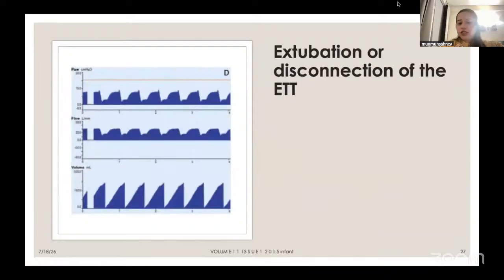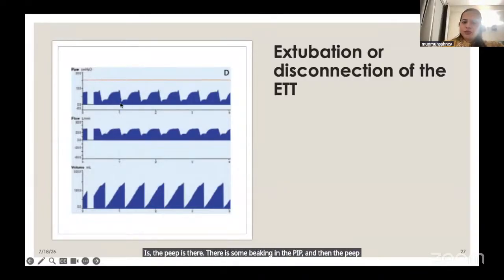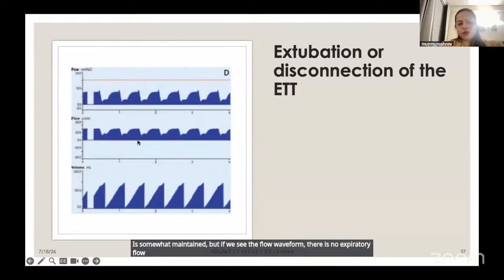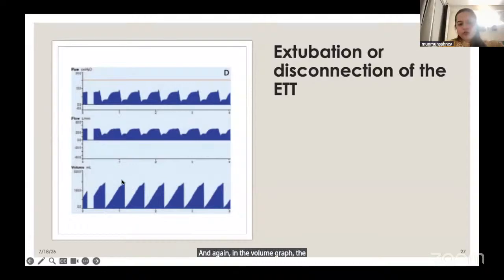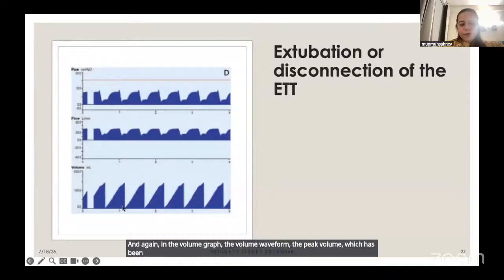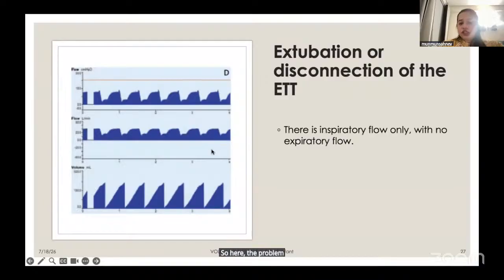The third and the last. Here, if we see the pressure waveform, there is some beaking in the PEEP, and then the PEEP is somewhat maintained. But if we see the flow waveform, there is no expiratory flow. The negative flow is not there. And again, in the volume graph, the peak volume which has been reached abruptly ends. So here the problem is around the ET tube.